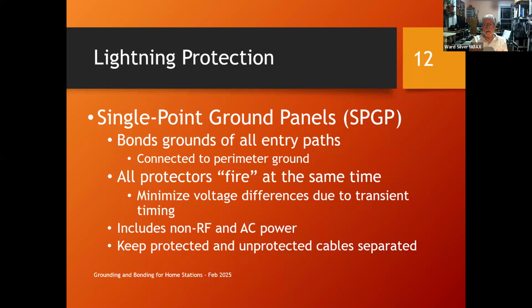If they don't all fire at the same time, you will have this point at a really high voltage while this arrestor has fired, and then a little later this one will fire, so it's down here, but this one is already done. So you have really high voltages between different ground points in your system, just because they're located at different points and the current doesn't flow at an infinite amount of speed. It flows at the speed of light, so you can have transient voltages that are quite significant between different ground terminals in your system.